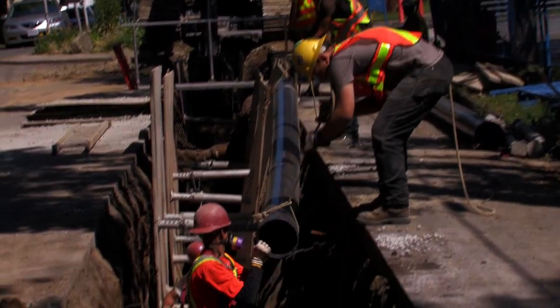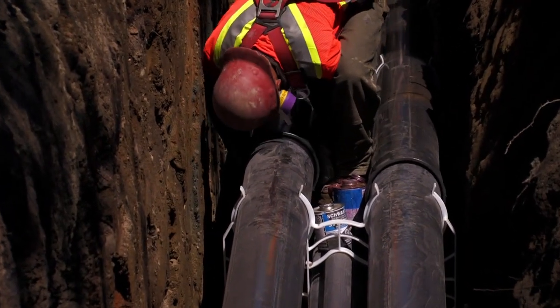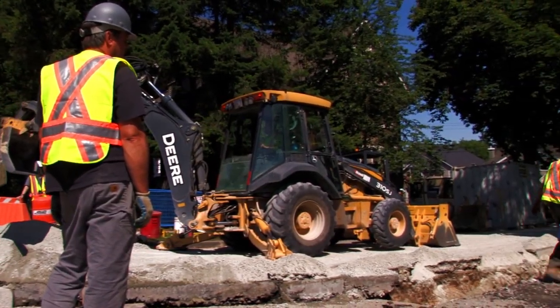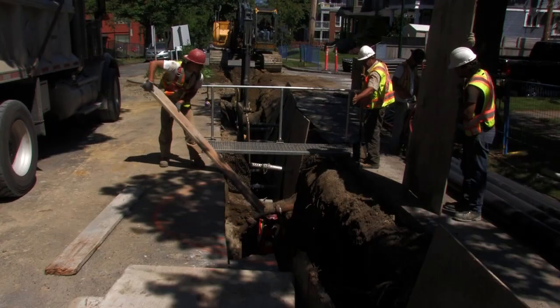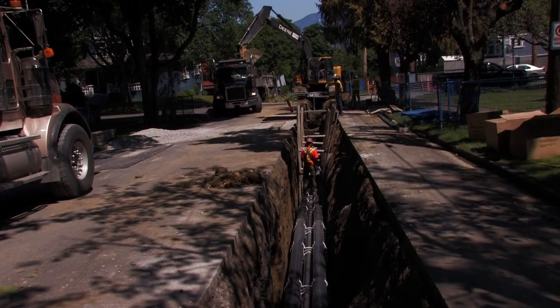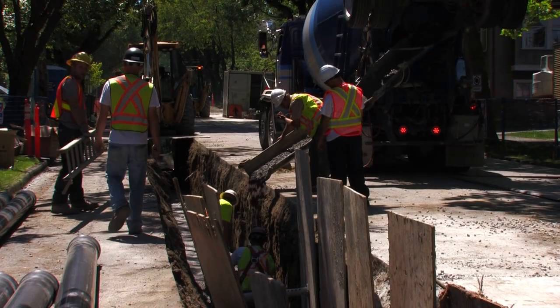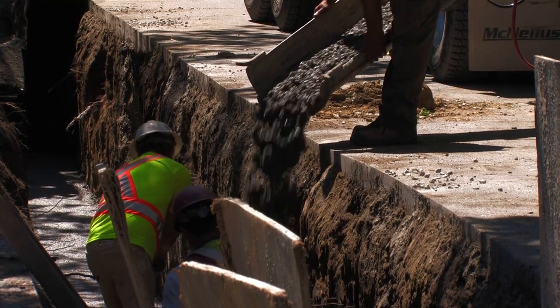The new line consists of two cable circuits that are made up of three 230-kilovolt cables. Crews safely completed duct bank construction despite many challenges, including avoidance of existing underground utilities such as water pipes, sewer pipes, and gas lines, variable soil conditions that were addressed using geotechnical engineering solutions, and coordination with City of Vancouver projects to reduce overall construction impacts.